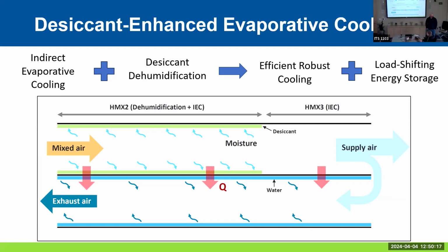Yeah. So I guess I'm just trying to imagine that if you have an indirect system during a heat wave event, you're able to rely on no compressor-based systems altogether. Well, unless you also need to regenerate the desiccant at the same time. Yeah, provided you have a big enough desiccant well that you don't need to regenerate it. Without the desiccant, in other words, this is adding an ability to avoid using a compressor altogether, or to use a more efficient, smaller compressor in the case of a heat pump regenerator, and then to avoid running that compressor during the load flex moment. Depending on the desiccant well, like you said.